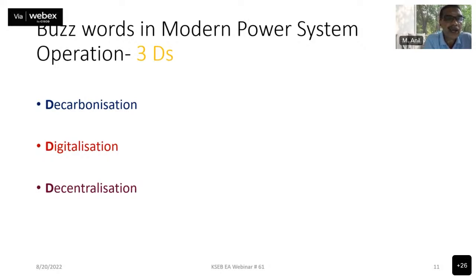Digitalization of grid. When we use SCADA systems or advanced communication systems with generation for capturing electrical data from the generating station to the central control station, load dispatch station or system operator station, that completes the digitalization of generating stations. In substations, we can have SAS, substation automation system, with the IEC 61850 protocol for maintaining digitalization in the transmission. Then distribution is the most difficult part. We need very wide investment, that is installation of smart meters, advanced metering infrastructure, etc. for digitalization of the distribution sector.